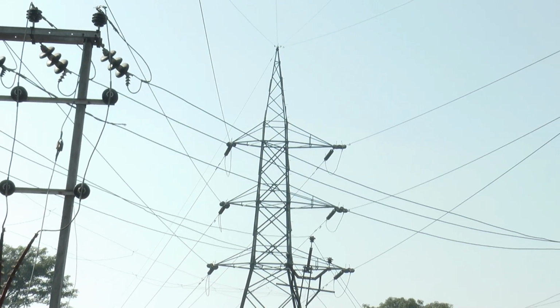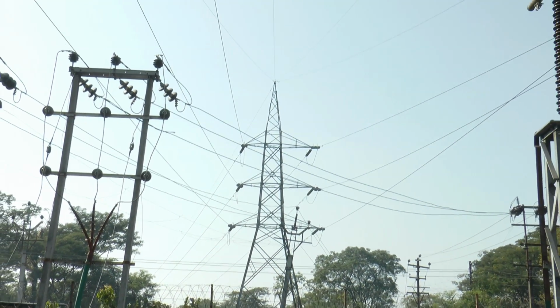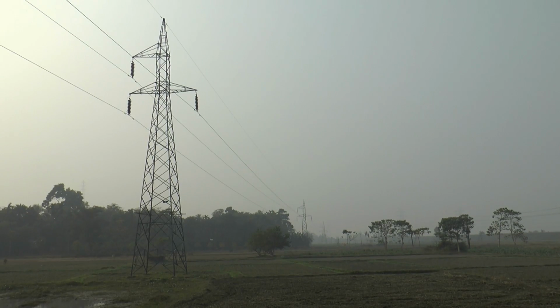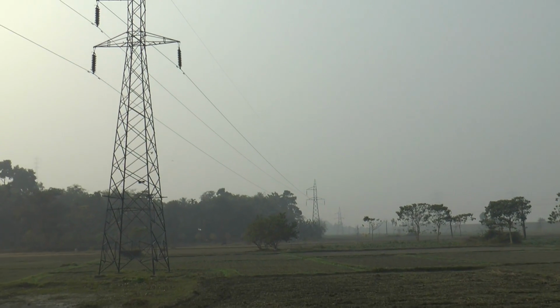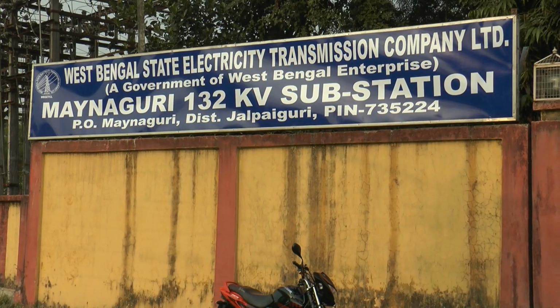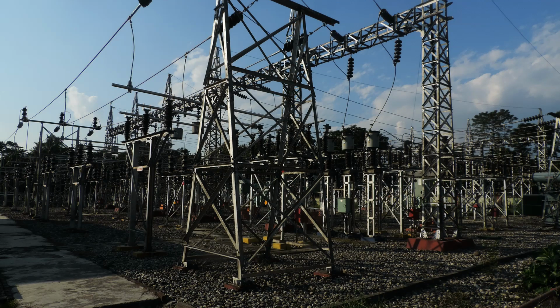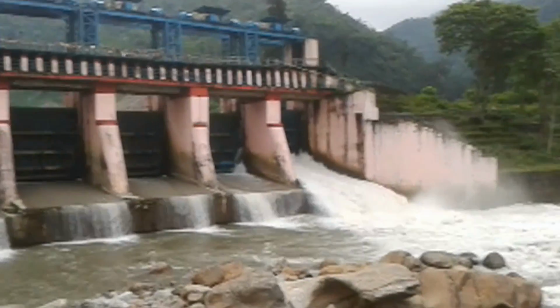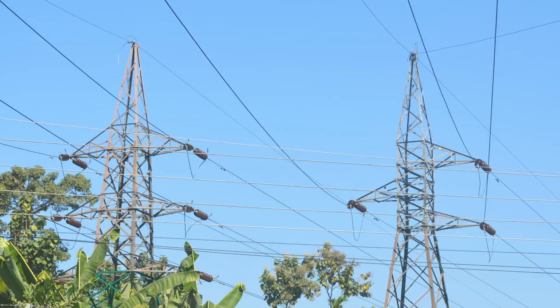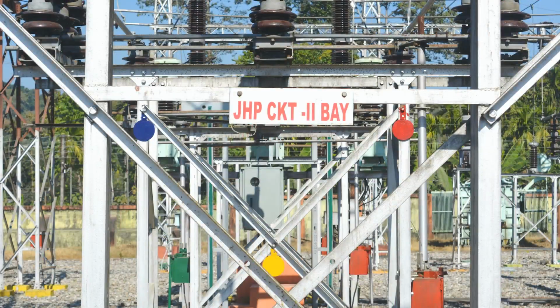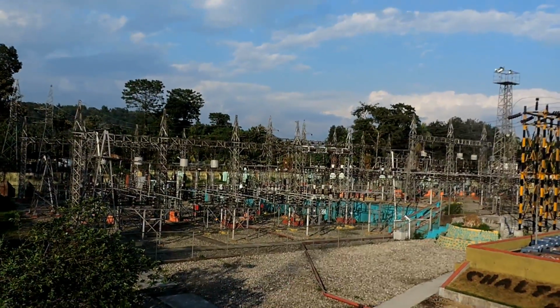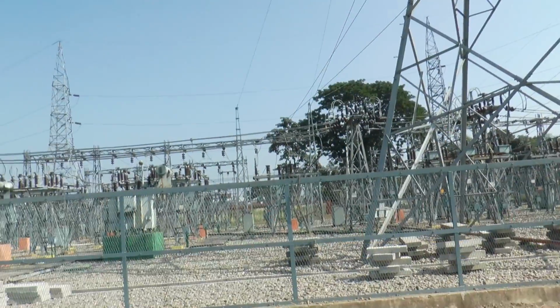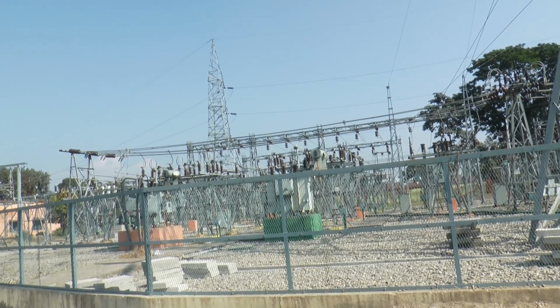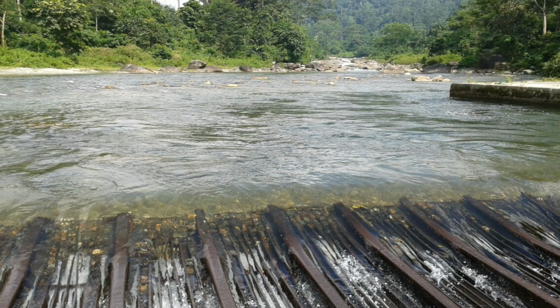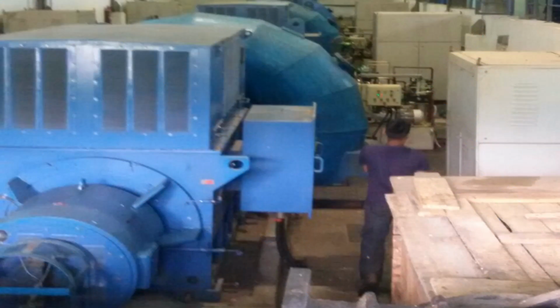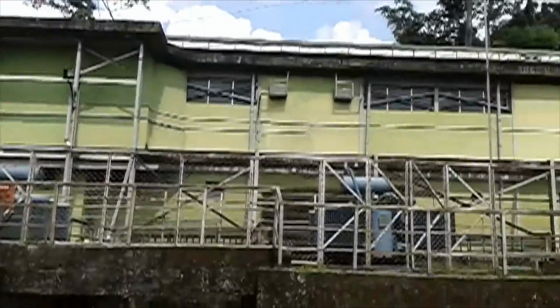At present, Chalsa 132 kV substation receives power at 132 kV from NJP 220 kV substation via Lilo of NJP Moinaguri 132 kV line, and can also receive power from 132 kV bus of Moinaguri 132 kV substation. This substation also evacuates the generating power of Jaldaka Hydel project at 66 kV via two 66 kV circuits, Jaldaka Circuit 1 and Circuit 2, which has an installed capacity of 44.9 MVA with a total of 6 units, 3 into 9 MVA plus 1 into 9.9 MVA plus 2 into 4 MVA. This substation also receives generating power at 11 kV from Neora Valley Hydel Power Station, which has an installed capacity of 3 MVA with a total of 3 units, 3 into 1 MVA.